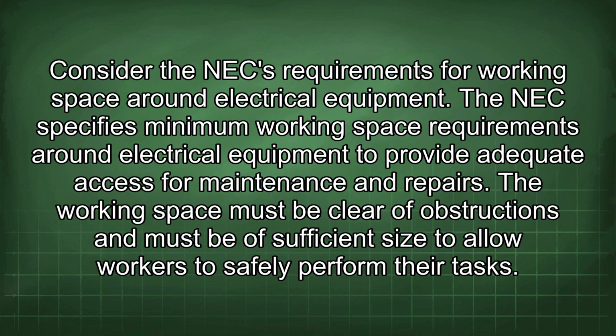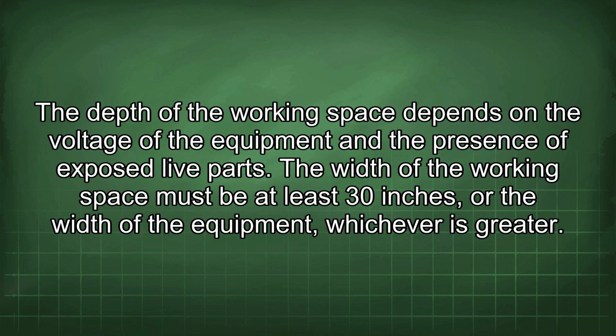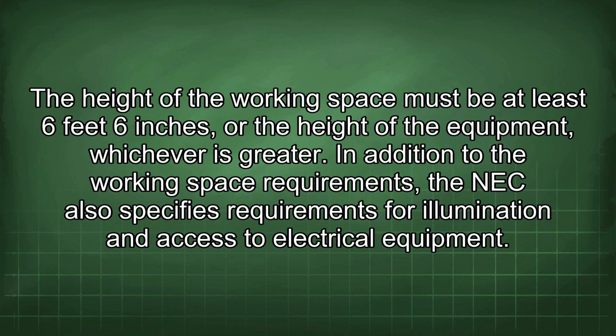Consider the NEC requirements for working space around electrical equipment. The NEC specifies minimum working space requirements around electrical equipment to provide adequate access for maintenance and repairs. The working space must be clear of obstructions and must be of sufficient size to allow workers to safely perform their tasks. The depth of the working space depends on the voltage of the equipment and the presence of exposed live parts. The width of the working space must be at least 30 inches, or the width of the equipment, whichever is greater. The height of the working space must be at least 6 feet 6 inches, or the height of the equipment, whichever is greater.